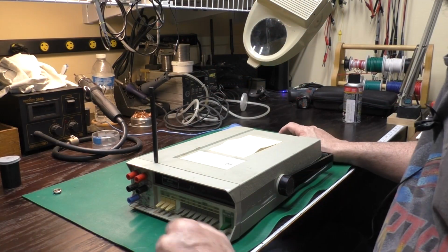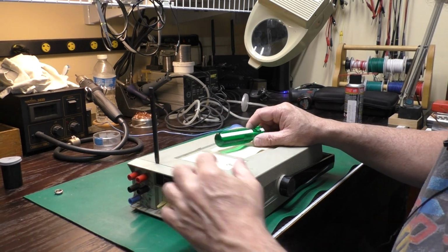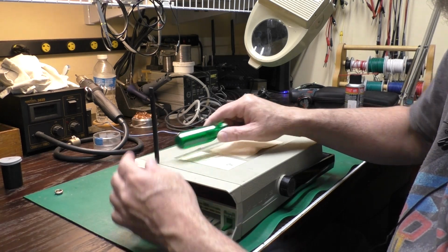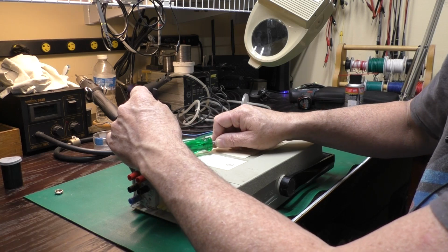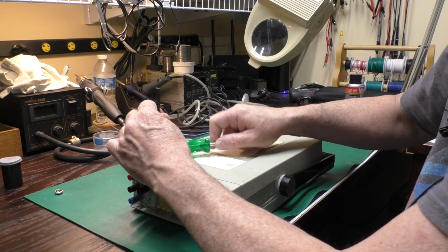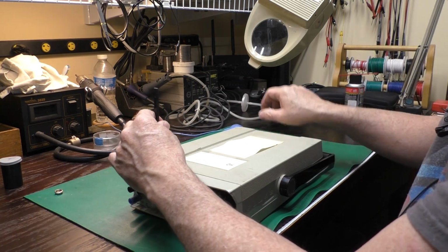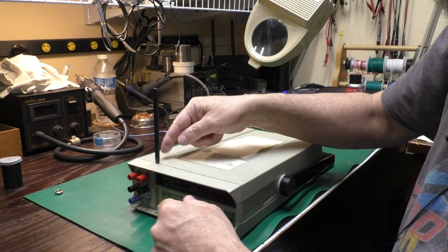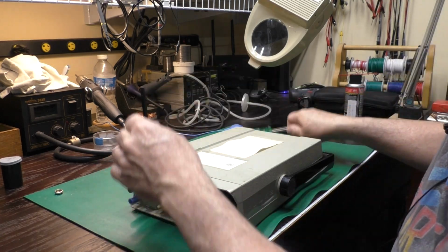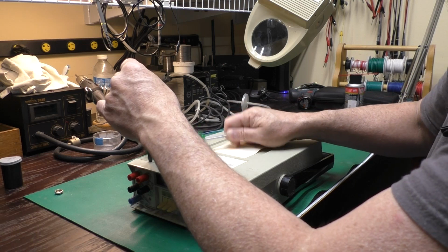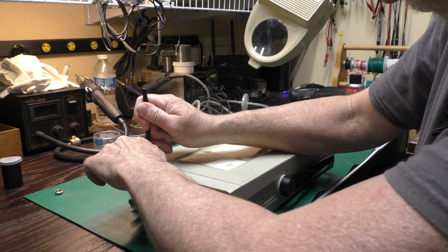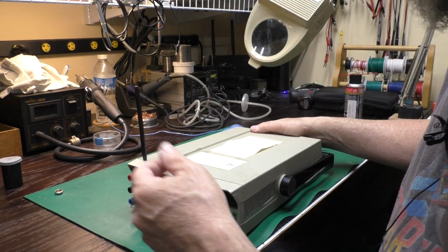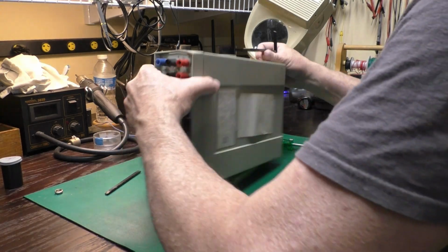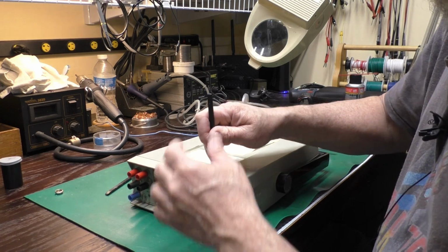Maybe I should read the directions. Bit of a different angle here to give me some more working room. What I'm doing is sliding a spudger along the crack in the front and tapping gently with a plastic screwdriver handle. So that puts a little pressure outward like this with the spudger, and the tapping just kind of helps loosen it up. According to the manual, it just says take out the 2 screws in the back that we took out and slide it apart. So who knows how many decades this thing's been stuck together. So I'll keep working at this, and then when I get it loose, we'll come back.